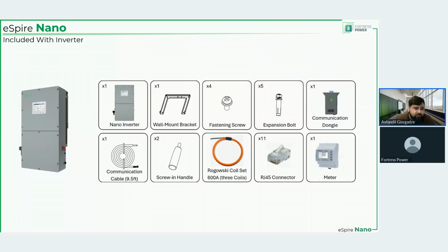9.5 feet is really enough, but not more than enough. So I want to have a longer cable in there, which will be useful for the people that don't necessarily mount the inverter onto the battery cabinet. So expect at some point to have a longer communication cable. Screw-in handles, which we will see in a moment, what they do and what's the value in having them. Rogowski coil set, 600 amps, 3 coils.